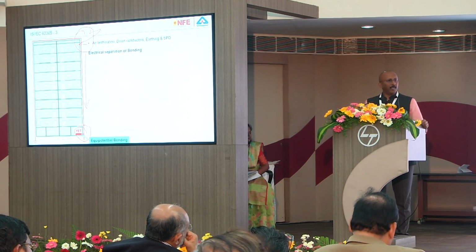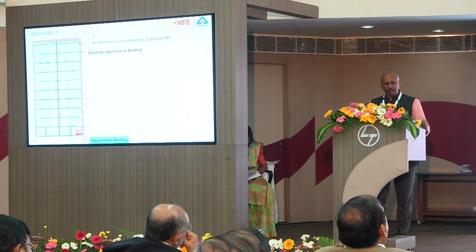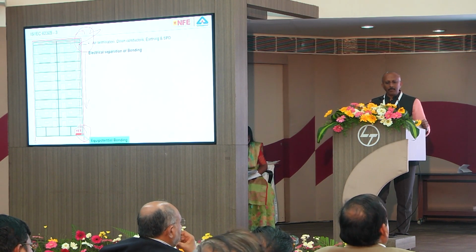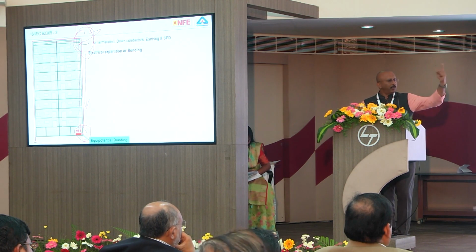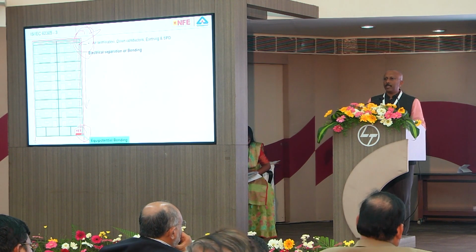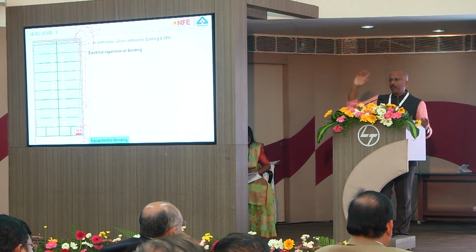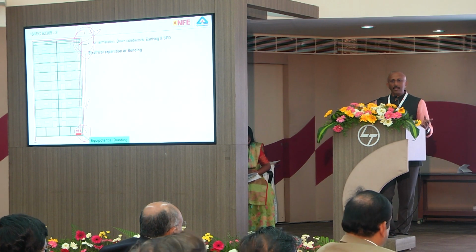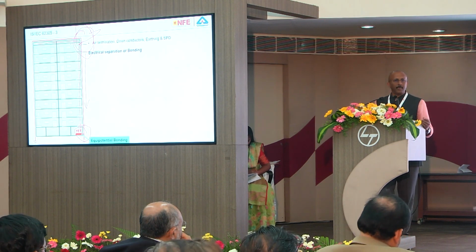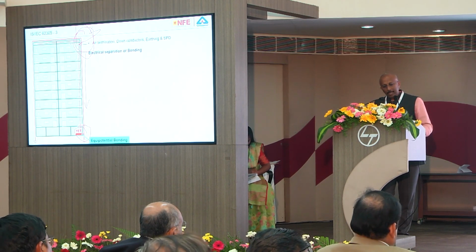Now where will this potential difference be applicable? For example, let us say there is a wiring inside the building. This wiring at this place where I have put the box, the round there, the air terminal which is just outside the building and the wiring inside the building will experience a high potential difference. There will be a direct flashover. So lightning has struck your conductor, but from the conductor inside your building there is a flashover. The result is the lightning now you have captured inside. The lightning has happened inside your building. This kind of flashover can happen to any apparatus, any metallic installations.